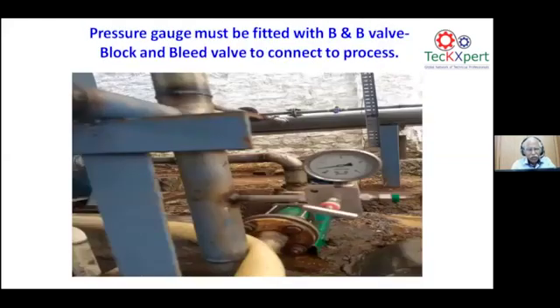For monitoring, again, everyone thinks pressure gauge monitoring is a very easy task, just to have a nipple and then just screw in the pressure gauge. It is not like that. Having worked in refineries for many years, we come across all the instrumentation installation standards. An ordinary pressure gauge also needs a block and bleed valve, because with it every month you can block the process and see whether the gauge is giving a zero, whether the zero is okay or the range is okay.